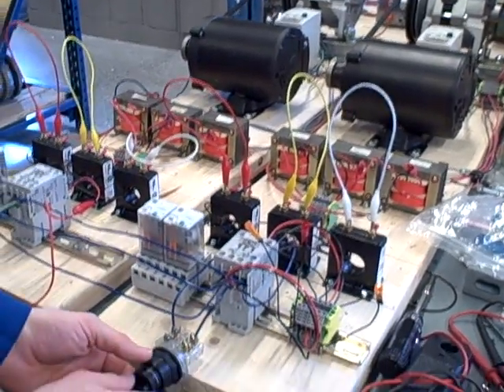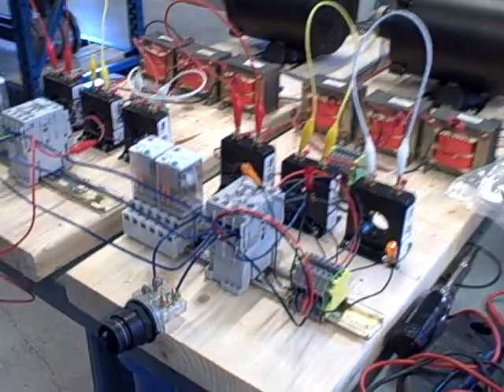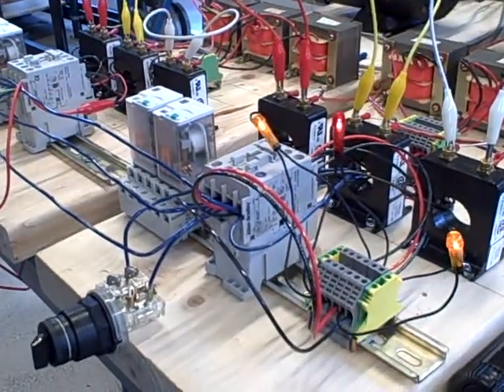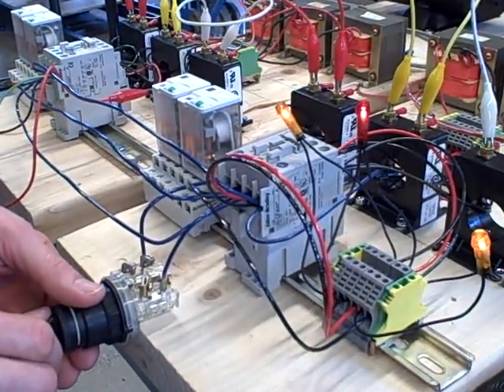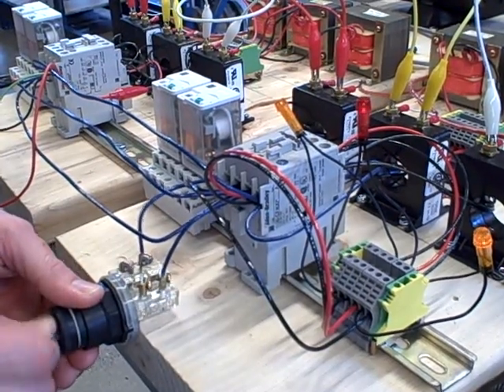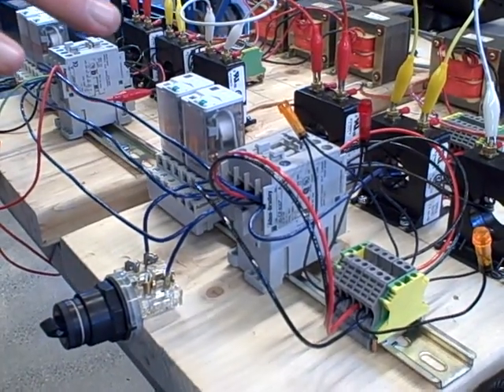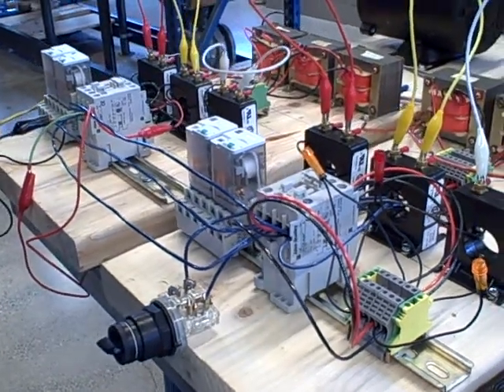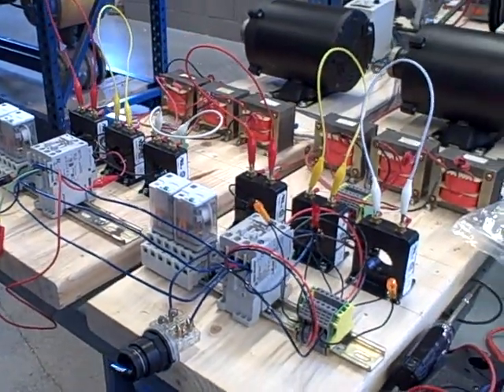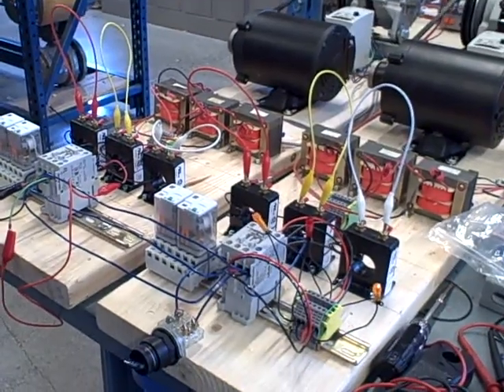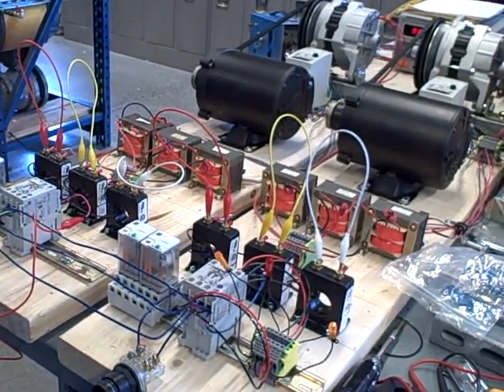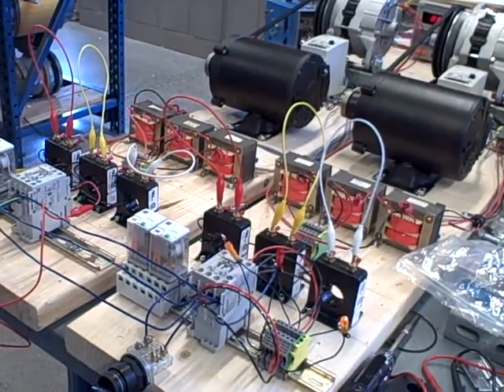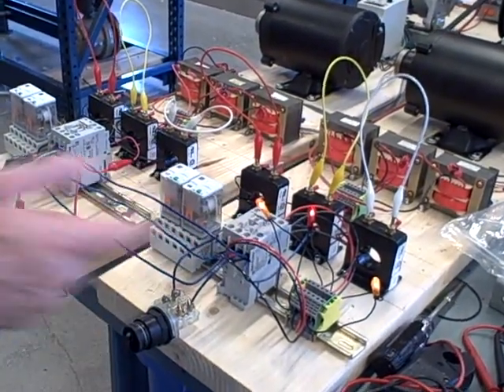I can unsynchronize the generators here, and you can see I go back into a condition where they're rolling in and out of phase with each other. I can go synchronize again, right there, and now they're synced with each other, and they're going to stay locked in sync unless I were to shut one down completely, because one generator in this case does not have enough current capacity to keep the other one going as a motor. That's a demonstration of synchronizing two generators and using sync lights to do so.